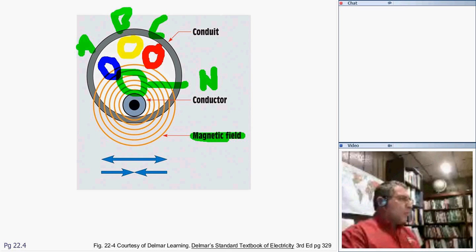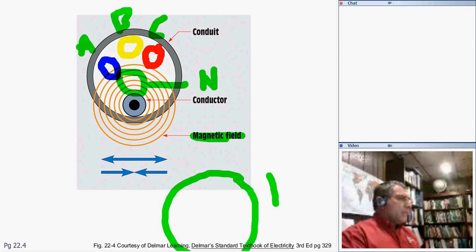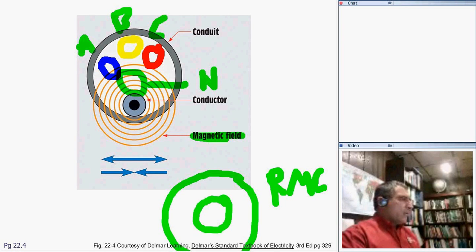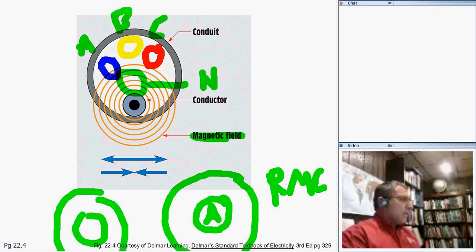Here's what you don't want to do. You don't want one conduit, especially steel. Steel is a rigid metal conduit. You don't bring one phase A conductor and put it in one conduit, and phase B conductor in another conduit, and phase C conductor in a third conduit, and the neutral in a fourth conduit. Do not do that by any means if it's a metallic conduit, especially steel. You can do this with PVC. It's not a good idea, but you can do it with PVC.